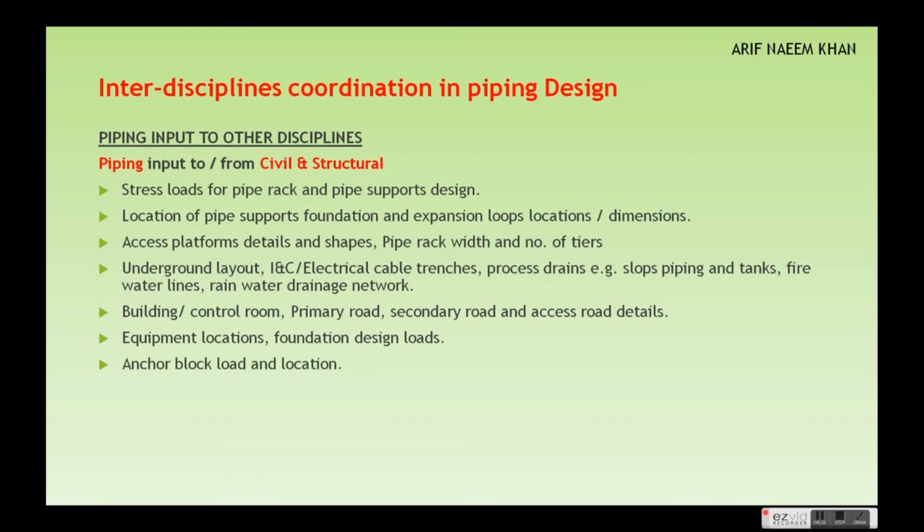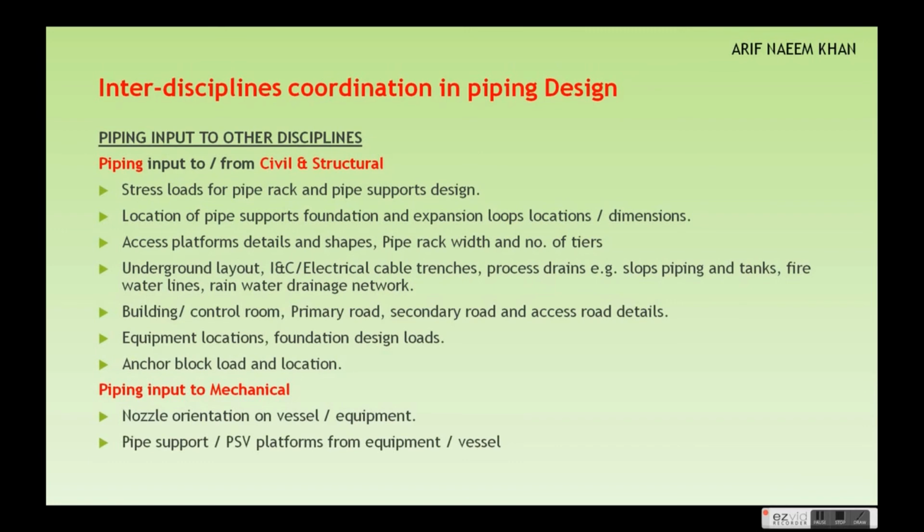Then anchor block locations and their loads. Then piping input to mechanical: nozzle orientation on vessels and equipment. This is very critical information that needs to be communicated from piping to mechanical. Piping will decide the nozzle orientation on the vessel. Then pipe supports for PSV platforms from the equipment or vessel: if we are taking any pipe support for the PSV from the equipment or vessel, we need to communicate with mechanical. Then bridle details and nozzle details are all input from piping to other disciplines.